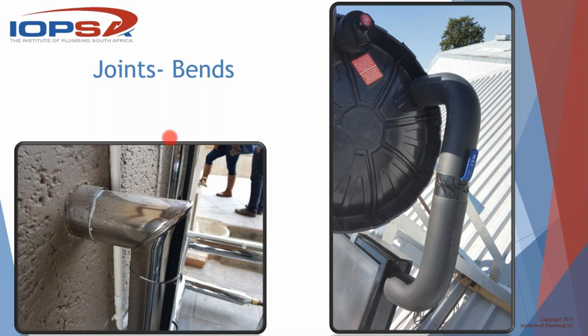And it's an incredibly good insulator, but it does need to be protected from the elements, i.e. water ingress, because it gets wet, same as glass wool. So you've got to protect it, and this is how they do it. And this is obviously mitered. The rock wool is not flexible enough for you to bend around anything. It'll just break. So you need to cut and miter and do the things properly, as opposed to this sort of thing where you can also cut and miter, but you can also force it around a large bend or a 45 degree bend or a 90 degree bend for that matter.